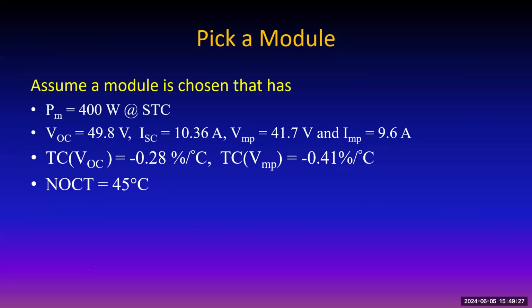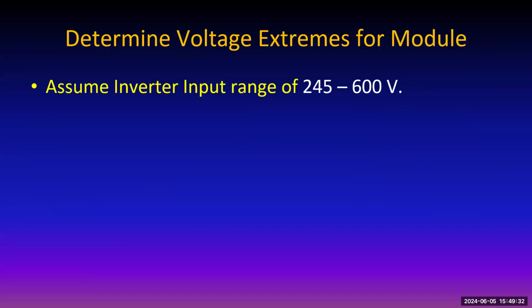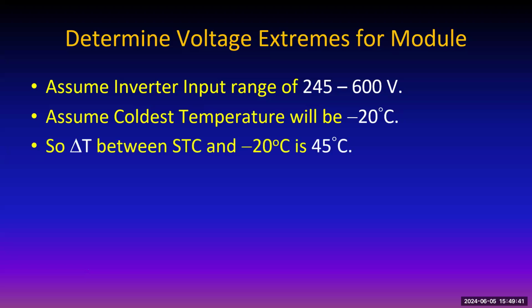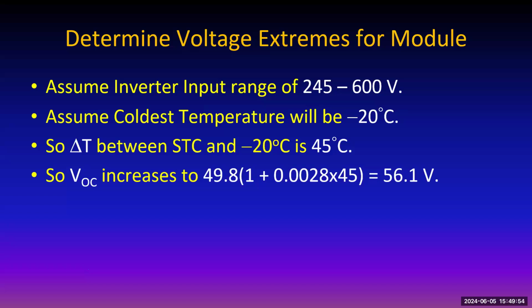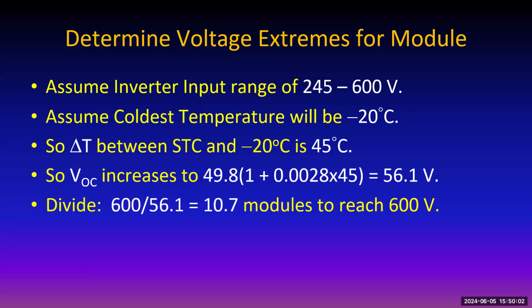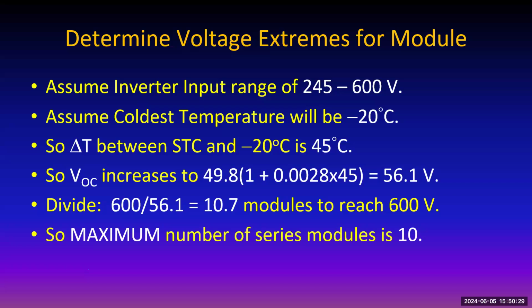Again, we've got our same friend, the same module, and we're going to look at voltage extremes. If the inverter input range is 245 to 600, and the coldest temperature is minus 20 C, then the temperature difference between the standard test conditions and minus 20 C is 45 degrees, because the modules are tested at 25 degrees C. The open circuit voltage increases by this formula and goes up to 56.1. That's okay. But then the maximum voltage, 600 divided by 56.1, says you can't have more than 10.7 modules. You better cut it back to 10, because 11 will give you more than 600. So you have to round down on this. That means your maximum string number of modules is 10. Sorry, 10, not 11.